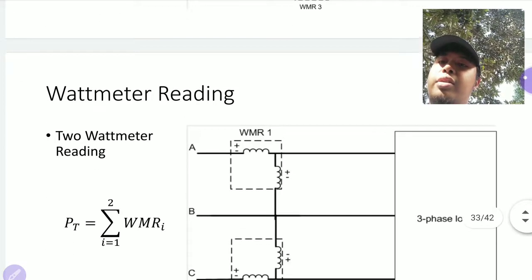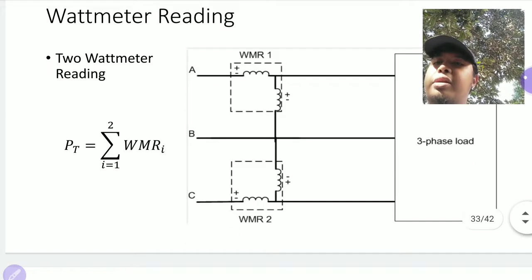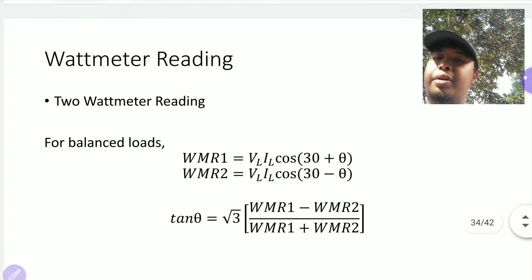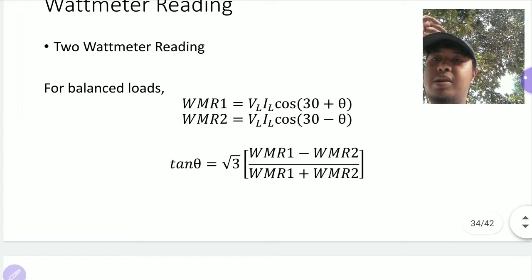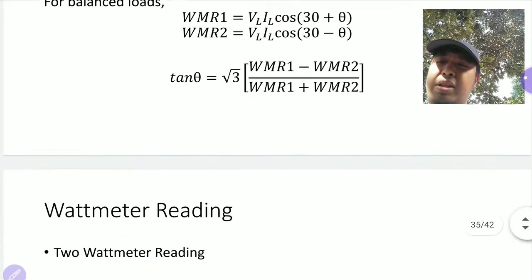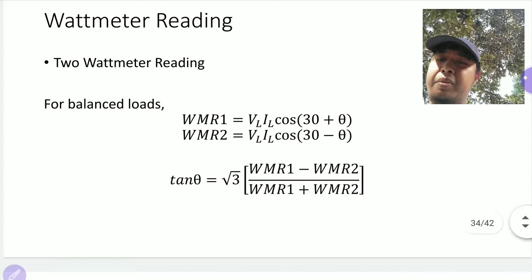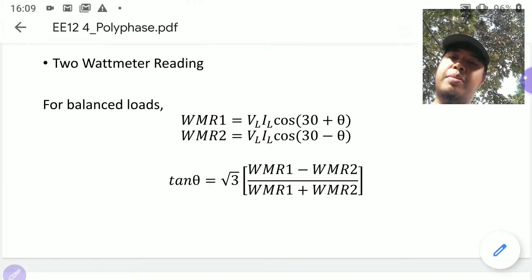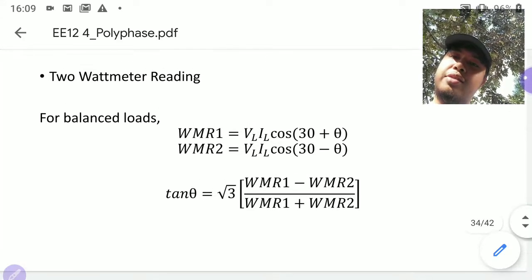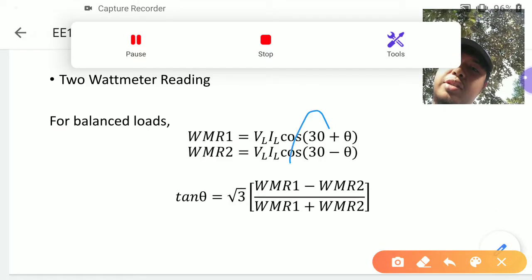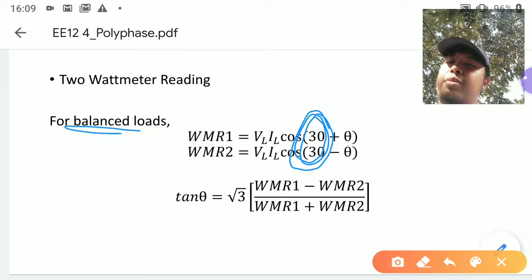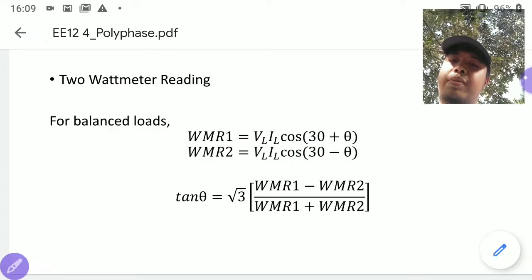So, to summarize: for the three-watt-meter method you use grounded systems with a neutral wire; for three-wire systems you use the two-watt-meter method. For balanced systems there is an equation involving a 30-degree offset — there is a diagram to describe this — but that 30-degree offset is only valid for balanced systems. If the system is not balanced you cannot use that equation.